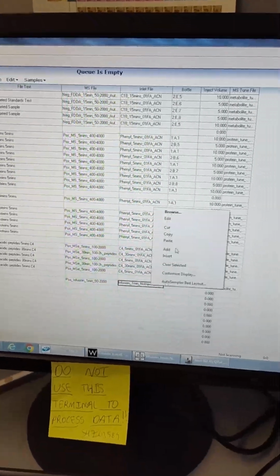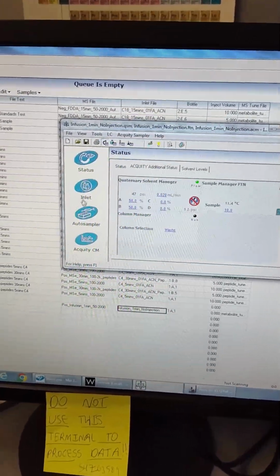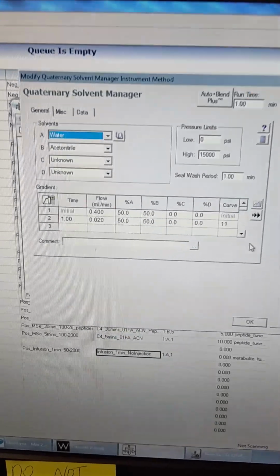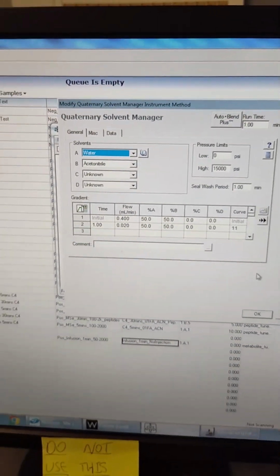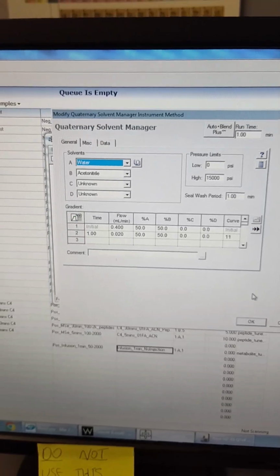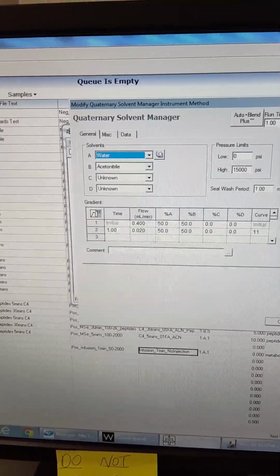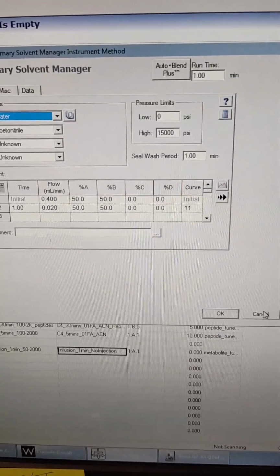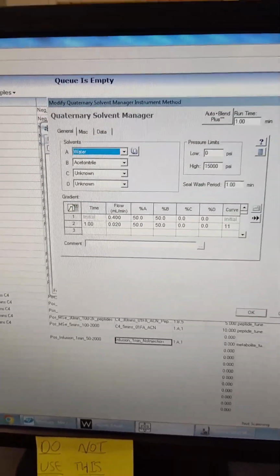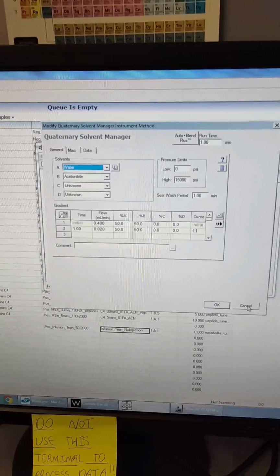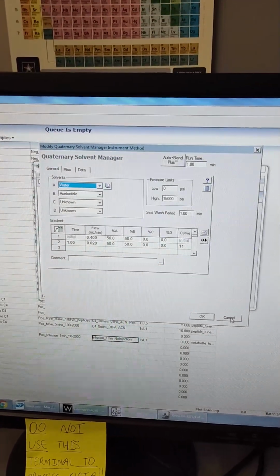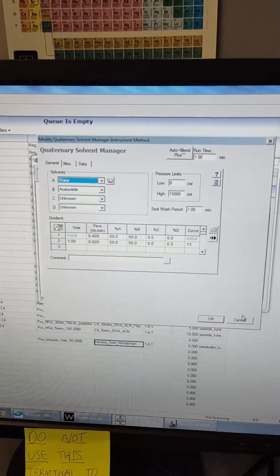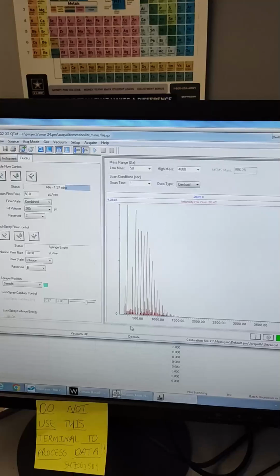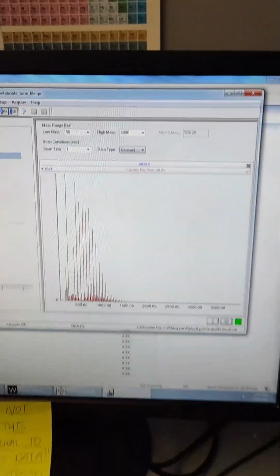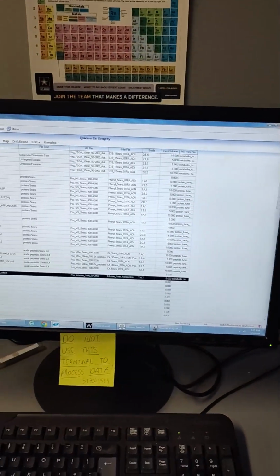And then if we look at the method here, we're going to have a flow rate of 0.4 mils per minute. This is a 50-50 0.1% formic acid water, acetonitrile. And then at the end, see we got the 11 on the curve. Right at the very end, it drops the flow rate down to 0.02 just to save solvent. But the whole flow is a combined infusion with your pump going at 0.4 mils a minute and the combined infusion on the syringe pump at 50 microliters a minute, and that gives you a nice signal with the right intensity so you can do the next step.